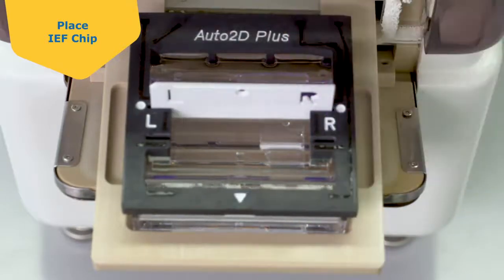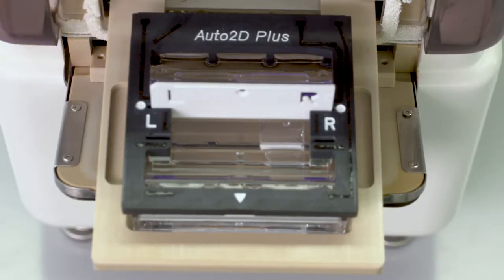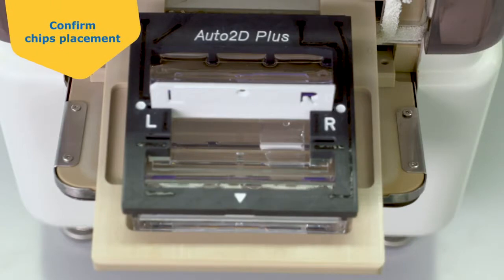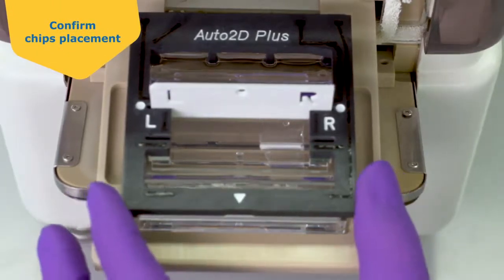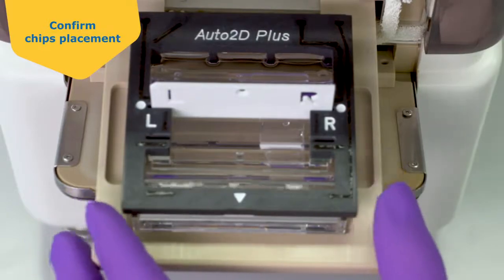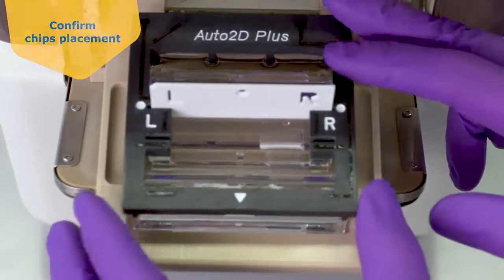Set the IEF chip into the Electrode Chip Plus slot marked with a white circle. Pay attention to the orientation of the IEF chip. The L should be on your left and the R should be on your right. After assembling the chips, confirm that the orientation of the IEF chip and the Solution Chip Plus are correct and that the Electrode Chip Plus is secure.